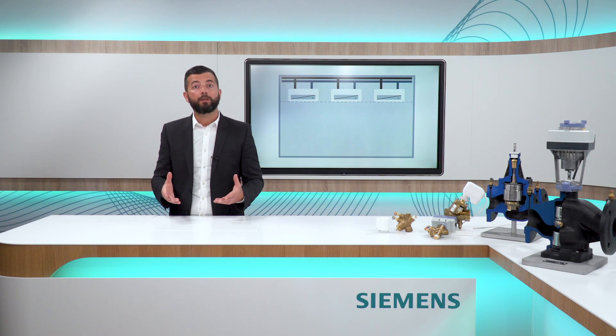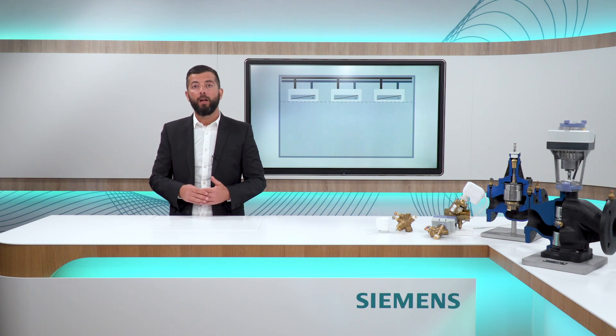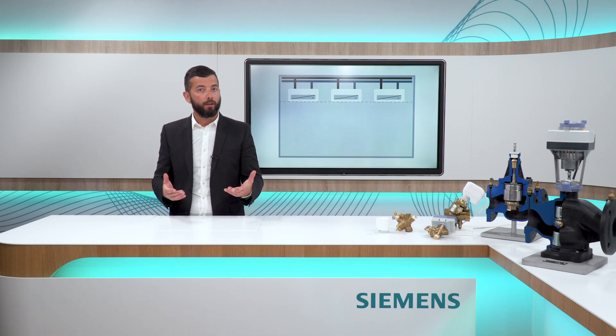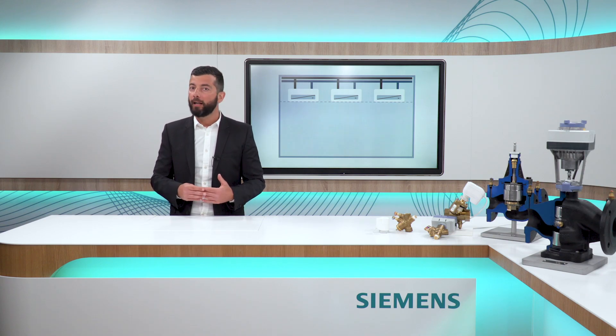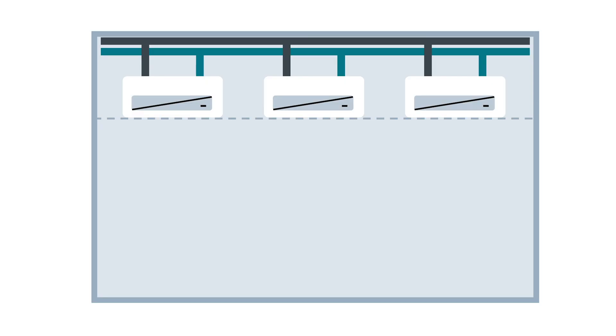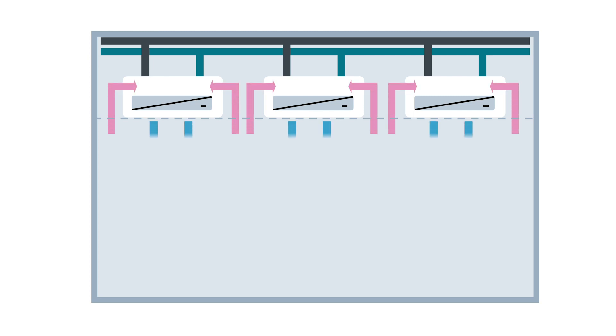The first type is called passive chilled beam, where water flows through a coil connected or welded to different kinds of metal plates or fins that cools down or heats up the nearby air and generates a constant air circulation by natural convection.